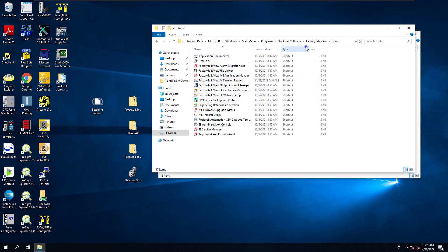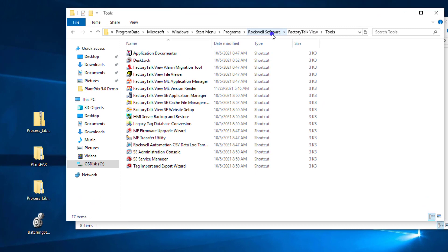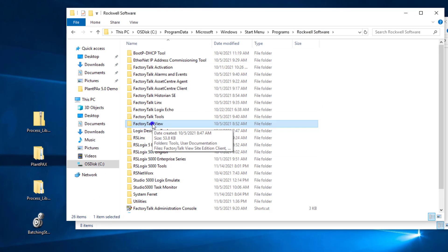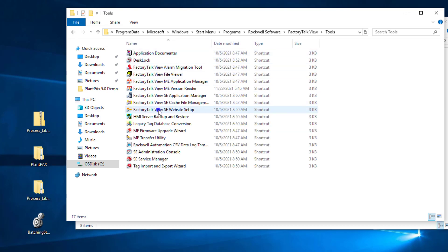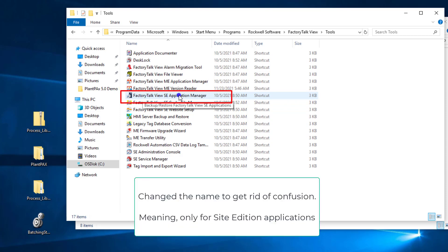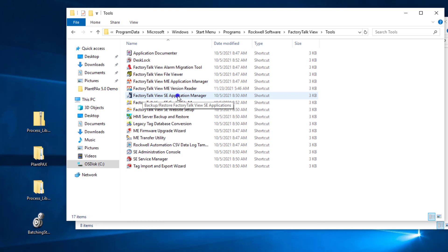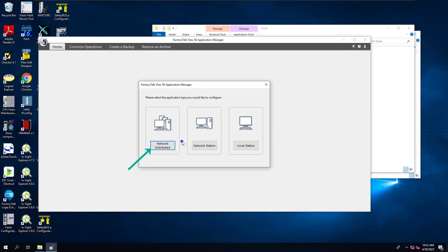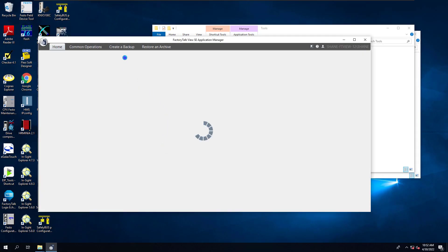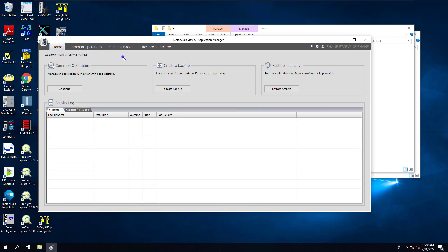Similar to what you would have done on Factory Talk 10, we're going to go to Rockwell Software, go to Factory Talk View, go to Tools, then go to what they've changed the name slightly - it's called Factory Talk View SE Application Manager. It's slightly different but they've changed the name just a little bit. You're going to open this up and click Distributed Network. With Factory Talk 12, they allow you the ability to back up more applications than just your distributed network - you can do locals and a couple of different things. So instead of Create Backup, we're going to Restore from Archive.